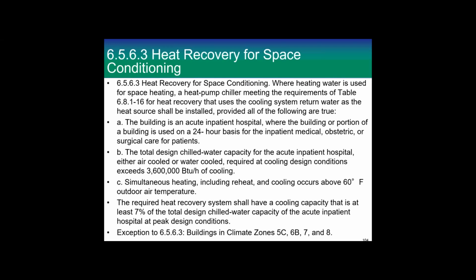There are some exceptions for certain climate zones where it just doesn't work psychrometrically, due to ones on the coast, ones in the dry section, and then 7 and 8 are in the very cold section. Now this was put forward by hospital people, and it is a good way to save energy in that location. Now what we normally do is put this in for these kind of spaces, and then see what our reactions are, get more data on them, and then try to start spreading this kind of thing.